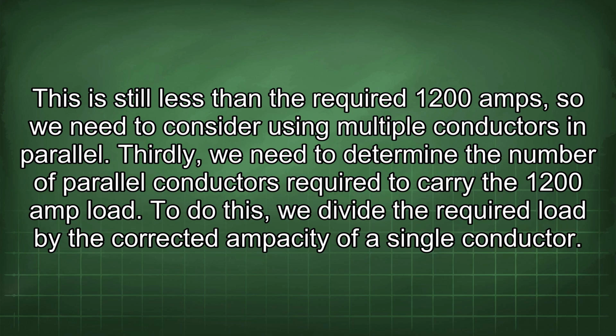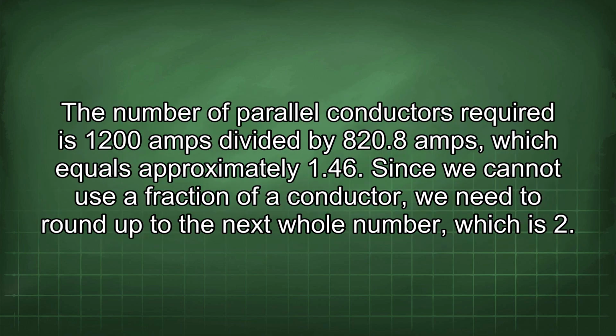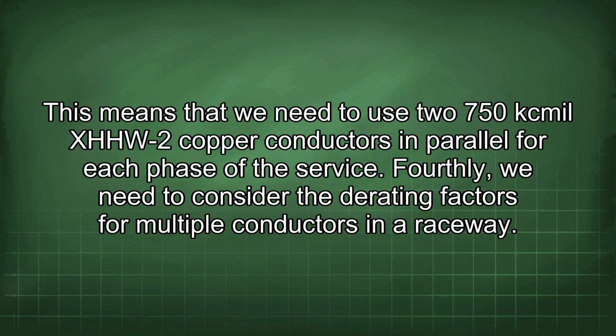Thirdly, we need to determine the number of parallel conductors required to carry the 1200 amp load. To do this, we divide the required load by the corrected ampacity of a single conductor. The number of parallel conductors required is 1200 amps divided by 820.8 amps, which equals approximately 1.46. Since we cannot use a fraction of a conductor, we need to round up to the next whole number, which is 2. This means that we need to use two 750 kcmil XHHW-2 copper conductors in parallel for each phase of the service.